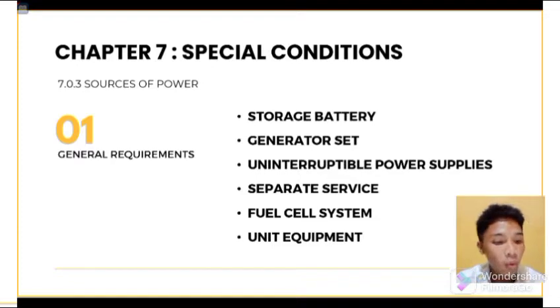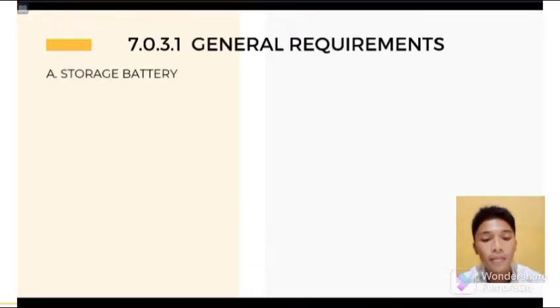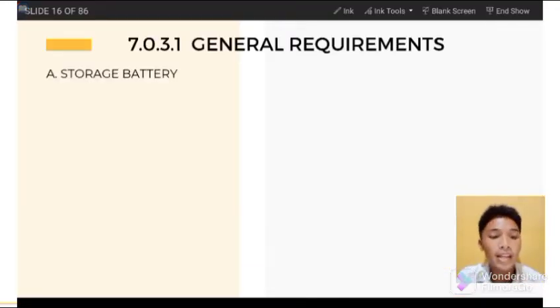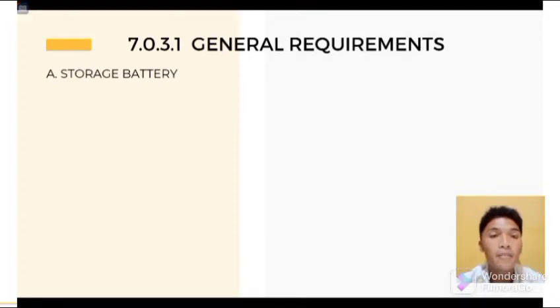Equipment shall be designed and located so as to minimize the hazards that might cause complete failure due to flooding, fires, icing, and vandalism. Storage battery. Storage batteries used as a source of power for emergency systems shall have a suitable rating and capacity to supply and maintain the total load for a minimum period of 1.5 hours, without the voltage applied to the load falling below 87.5% of the normal.